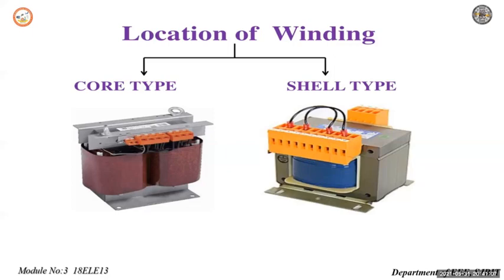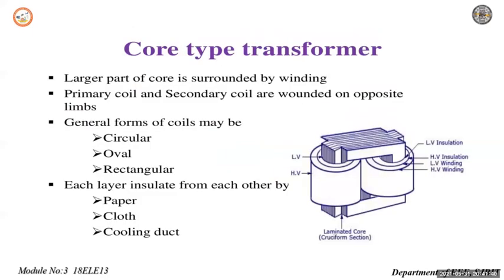The core is laminated. While arranging the laminations of the core, care is taken that all the joints at alternate layers are staggered. This is done to avoid a narrow air gap at the joint right through the cross section of the core. Generally, for very high voltage transformers, the shell type construction is preferred. As the windings are surrounded by the core, the natural cooling does not exist.